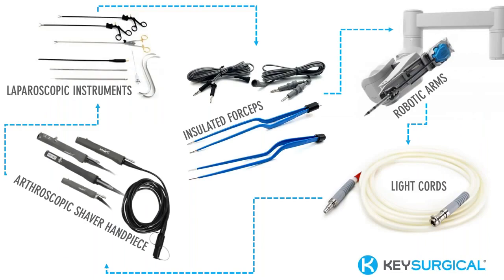So we see what electrosurgery looks like for the operating room. There's a lot of detail, and there's actually a patient there in front of you. From the sterile processing perspective, what does electrosurgery look like for us? While I know not all these instruments are necessarily electrosurgical instruments like the laparoscopic instruments or the insulated forceps, they have electrical components that may affect the patient in the procedure. So in sterile processing, we must diligently inspect all aspects of not only laparoscopic and insulated forceps, but robotic arms and cords, which are often hand washed. Light cords are also hand washed. If these are cracked or broken, they can be an ignition source. And lastly, arthroscopic shaver handpieces, which I'm sure you in the operating room world and nurses have seen every single one of these instruments. So this is what it looks like from a sterile processing perspective, a little bit different.